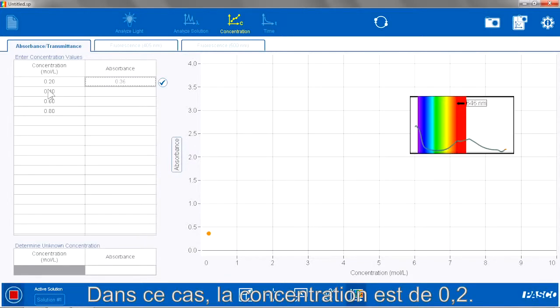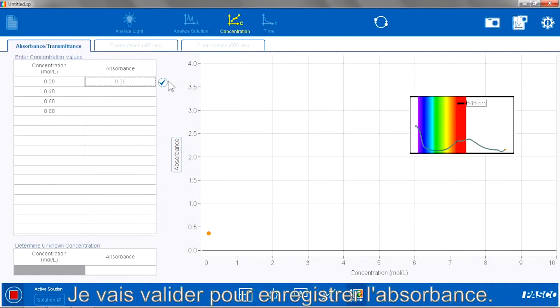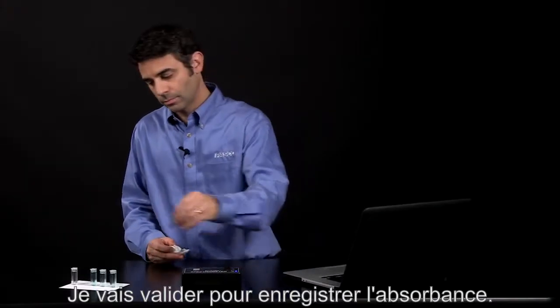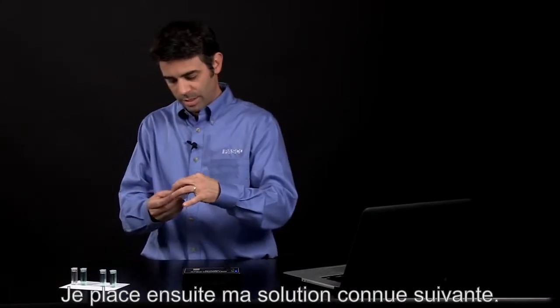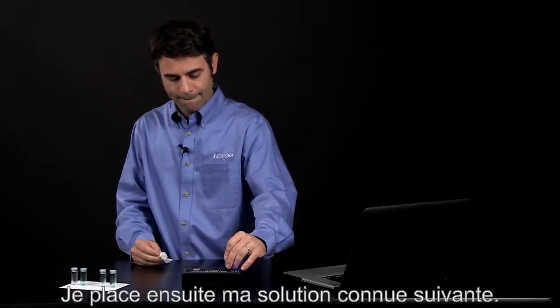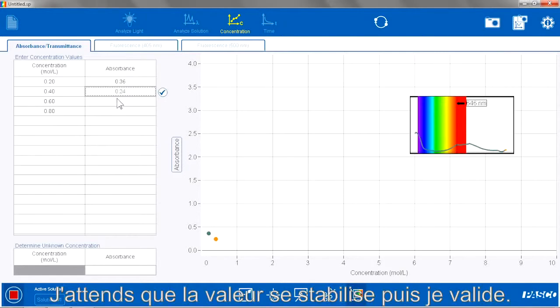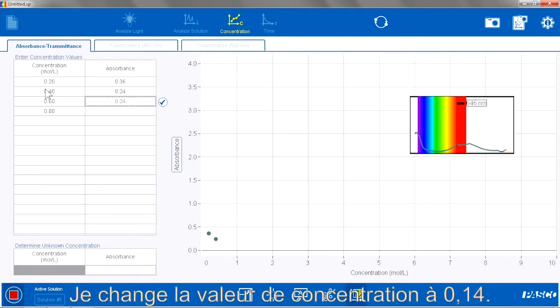And in this case, it actually is 0.2 for the concentration. So I'm going to hit Check to save that absorbance. I'm going to put in my next standard. I'm going to wait for that to stabilize, and I'm going to hit Check. I'm going to change the concentration value to 0.14.